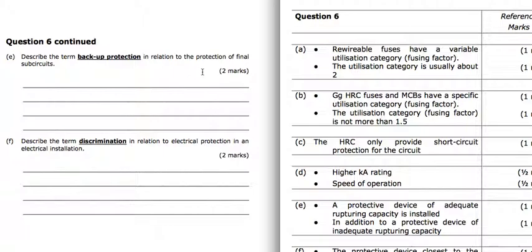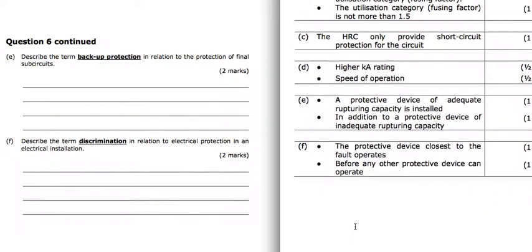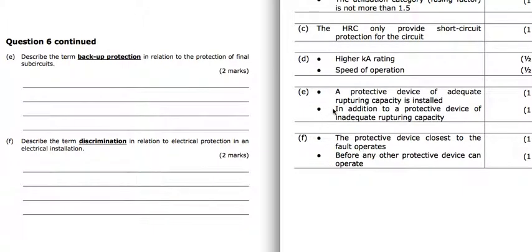Describe the term backup protection in relation to the protection of final subcircuits. So we would have another fuse in the circuit that would supplement the normal fuses in there, or an MCB. If there's an MCB, it won't have the rupturing capacity of the circuit maybe. So there'll be a high prospective short circuit current, and that MCB cannot handle that current, and so we put an HRC fuse in there, for instance, that backs up the MCB because that has the high rupturing capacity. So it's a protective device using an HRC fuse of adequate rupturing capacity in addition to the protective device of inadequate rupturing capacity. Term discrimination, so that's all about the protective device closest to the fault operating before any of the other protective devices.